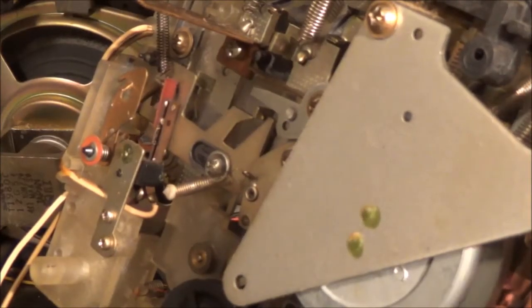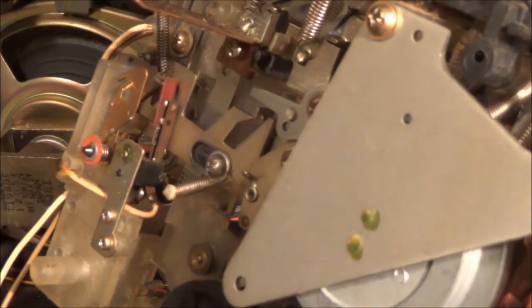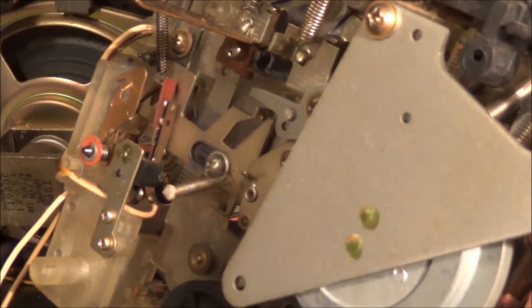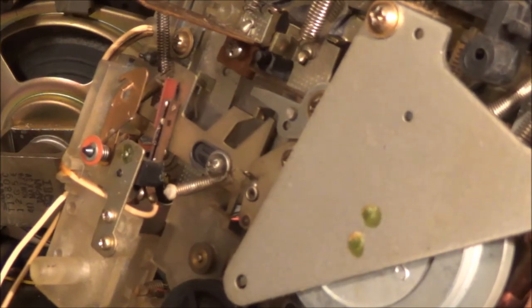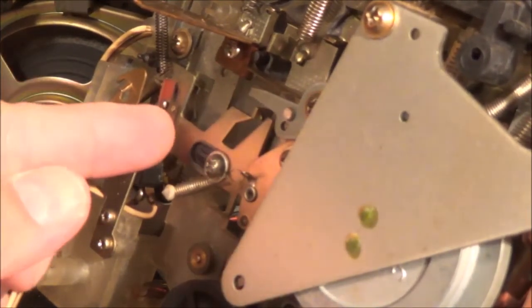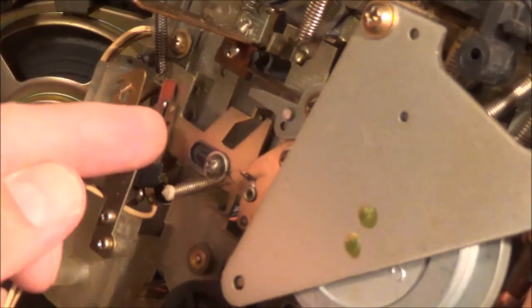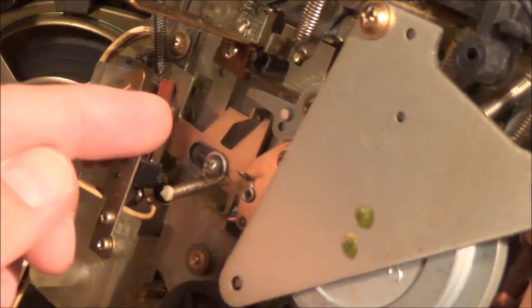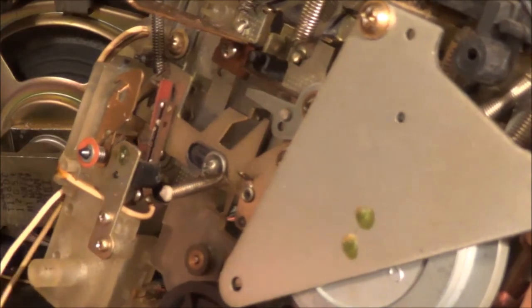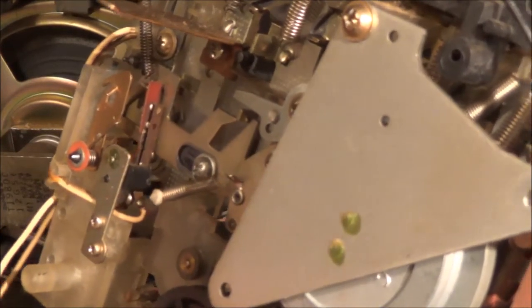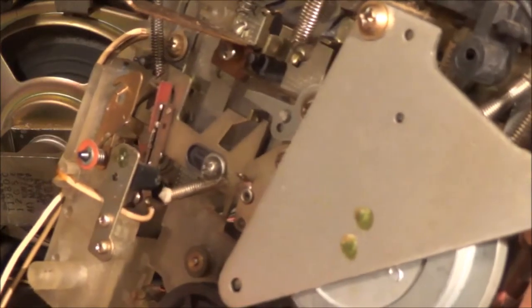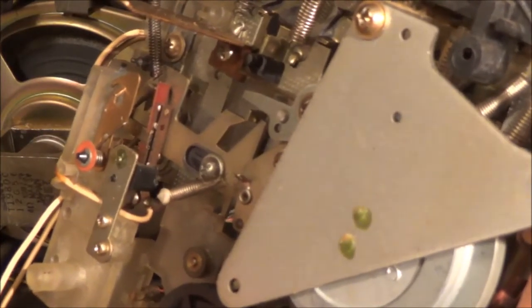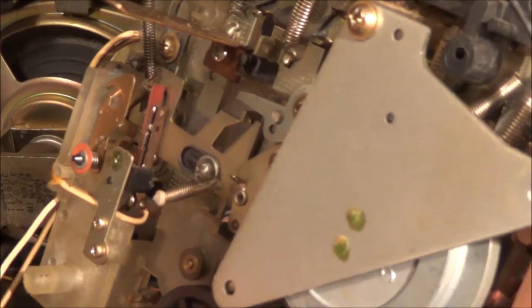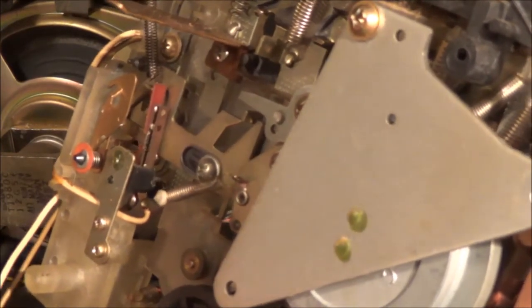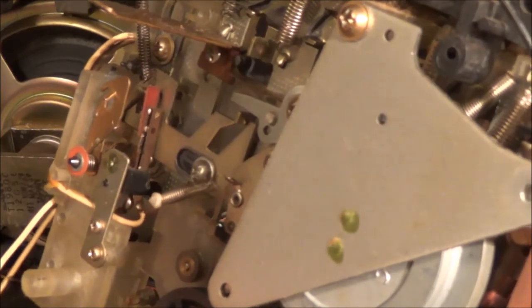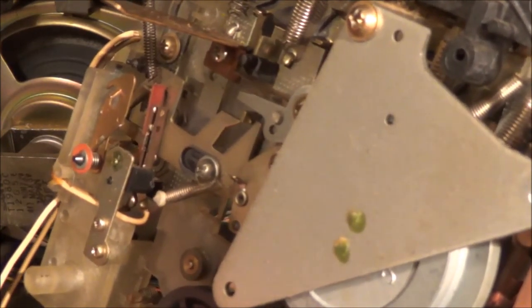So again, if you are not getting voltage up to the motor, and you've got the motor disconnected, measuring from the wires, you've got to be sure to check this motor switch here — the leaf switch. A lot of times you might have a problem with that, and then basically you just got to work your way back. Sometimes you've got motor control circuits, and you just got to see what they're putting out. Theoretically you could have a motor running too fast too, but I've never run across that. I'd go ahead and check if it's got any electronic control circuits there, and make some measurements.